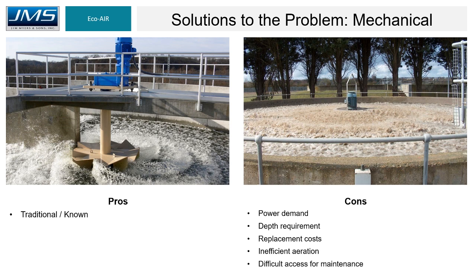The traditional mechanical aerator is an established, well-known piece of equipment that has been used for a long time. However, some cons include high power demand, a deeper water depth requirement, potentially inefficient aeration, difficult access for maintenance, and a potentially high replacement cost.